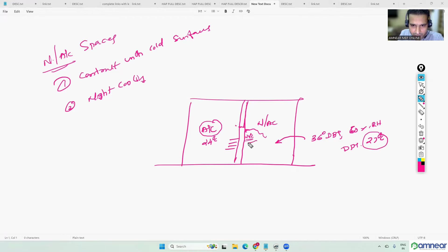And at nighttime also this issue can come. At nighttime, for example, it is an unconditioned space. I am having a window there, and condensation can come inside and outside. Normally for air conditioned spaces, it will be happening outside if you're having a glass window. Okay, I'm having an AC room. It is a glass window. Inside I might be having 24 degrees Celsius, but the atmosphere is having 36 degrees Celsius and 60% RH. On that state, dew point temperature is 27. But inside the room, I am having 24. Outside, it is 27. So when the atmosphere is having contact with the building glass, the glass surface temperature is somewhat near to 24 only. What will happen? Condensation issue can come. That will happen on the outside.